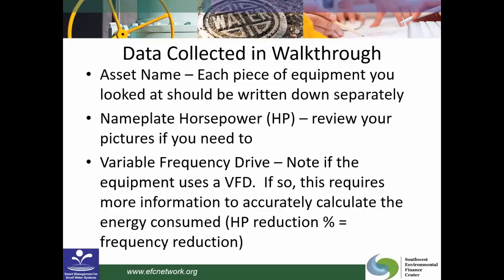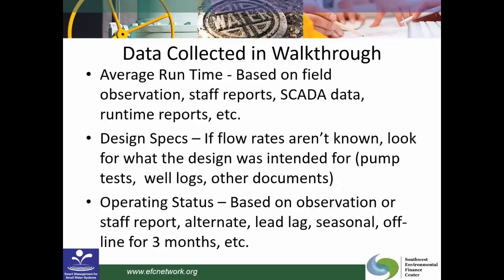And also you want to note if the pump or motor is using a variable frequency drive. If it does, it will affect the way that you do your calculations. So your horsepower reduction percentage is equal to the frequency reduction. So just be aware that if you're using a VFD, it will impact the way that you calculate your usage.